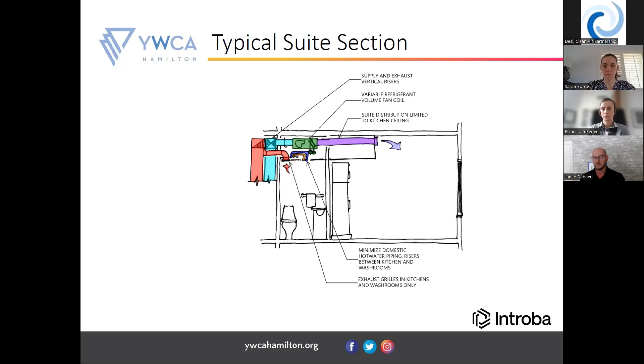In passive houses, you have to have quite a bit of insulation on domestic cold and hot water, about twice as big as a standard ASHRAE 90.1 allowance. So we did have to do quite a bit of extra layout for that piping, as well as the risers. We normally don't have risers, so putting the fan coils into the ceiling saves space, but you do have these risers running through the building.